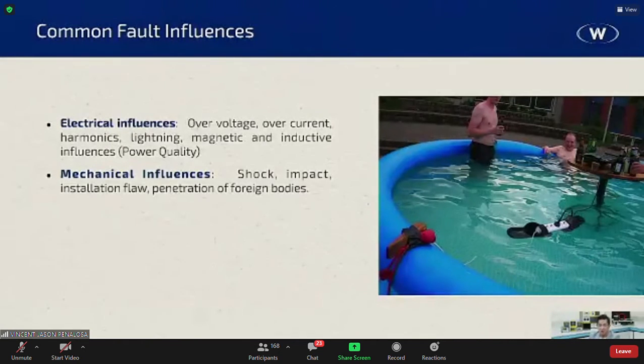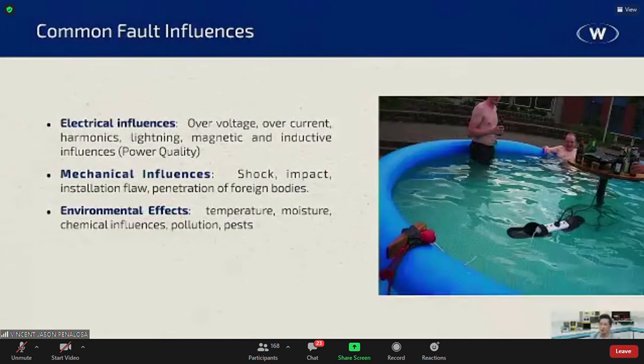Now, mechanical influences: shock, impact, installation flaws, penetration of foreign bodies. Environmental effects: temperature, of course, where we live, it's not the coldest part in the world. If you have a lot of moisture in the atmosphere of your workplace, let's say near the sea, that atmosphere is also corrosive, right? Chemical influences: in operating theaters, their cleaning solutions are quite corrosive as well, because they are quite strong. And then you also have pollution and pests. The pollution creates some sort of capacitance between the conductors and sometimes to ground, depending on how bad the pollution is. And of course, the pests. I don't know why the rodents love the cables, they love nibbling on them. And then you have equipment aging, and lastly, you have unsafe practice.